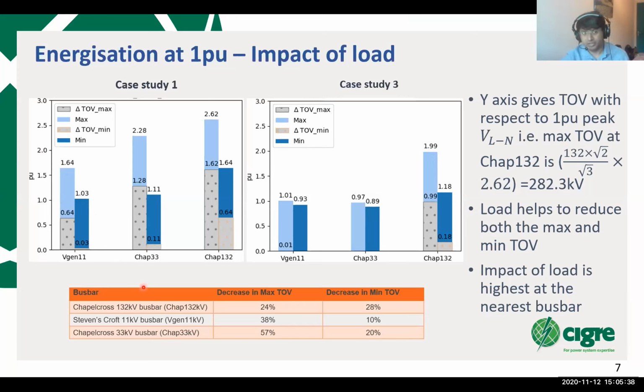Once again, to interpret this graph, on the y-axis we have the per unit temporary overvoltage observed at these bus bars. These are calculated in per unit in terms of the phase, 1 per unit phase voltage. So if you have to calculate the absolute value of the voltage, this is how we have to calculate it based on the per unit value that we observe here.